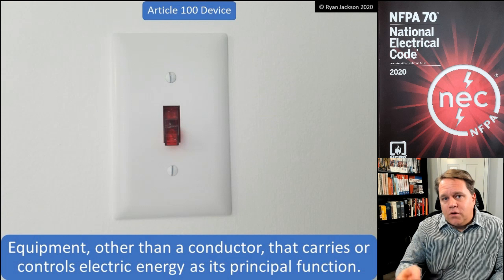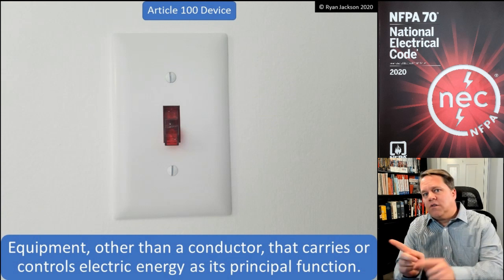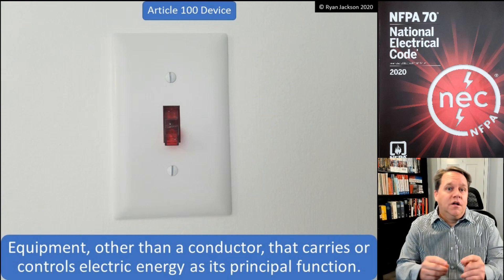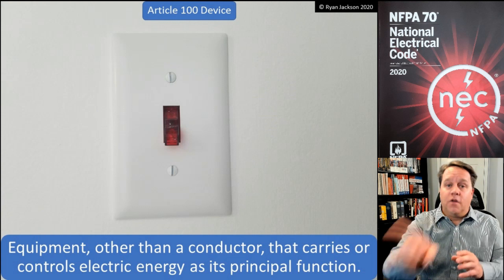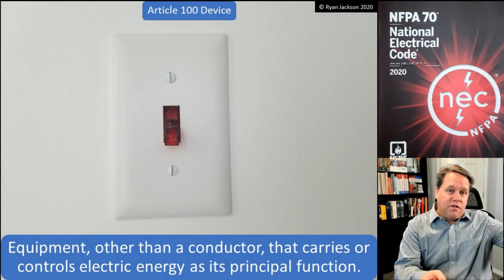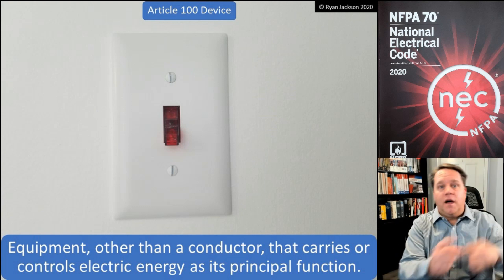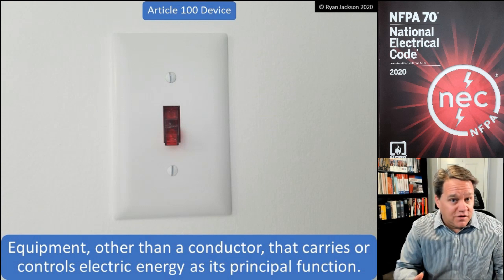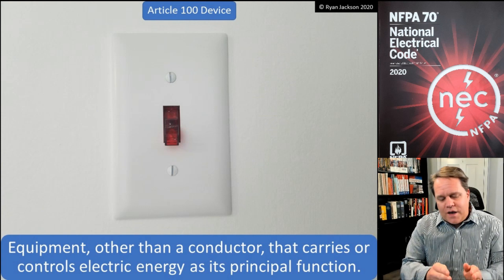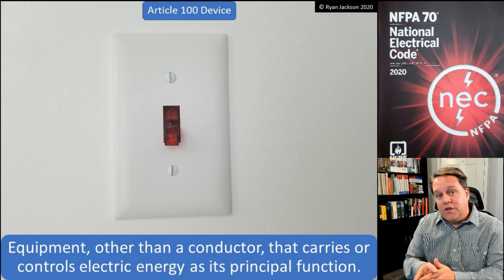But then the question was, is a switch an outlet? And it was like no, it's a device. But what if you had the switch for the bedroom in the hallway and the outlet is in the bedroom? Would the switch be AFCI? And you had all sorts of crazy different things. So as we have requirements, we tweak the definition.